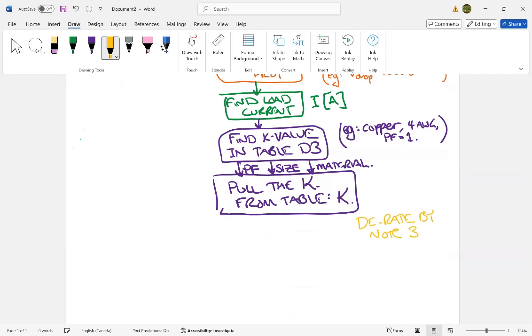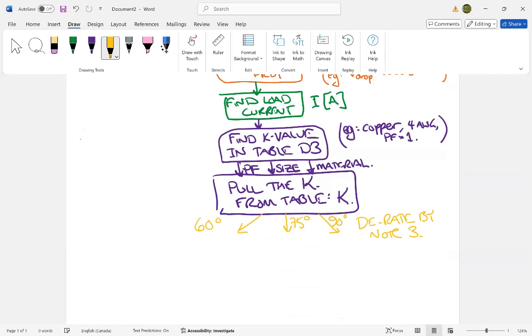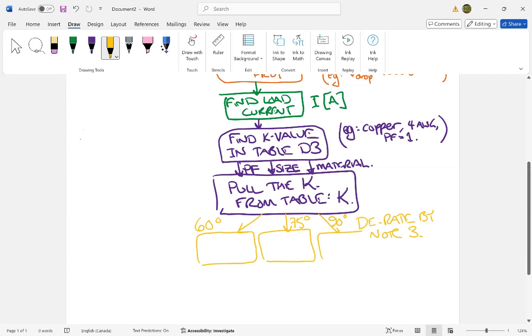Okay, so note three says that if it is 60 degrees, you do something. If it is 75 degrees, you do something. If it is 90 degrees, you do something. And what's in the table is actually just the 75 degree case. So here is your factor that you multiply K by, and since the table itself is for 75 degrees, then I'll say multiply by one, unity.